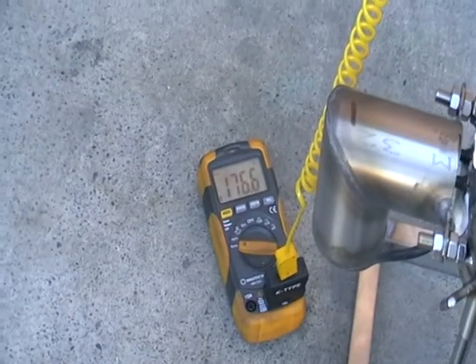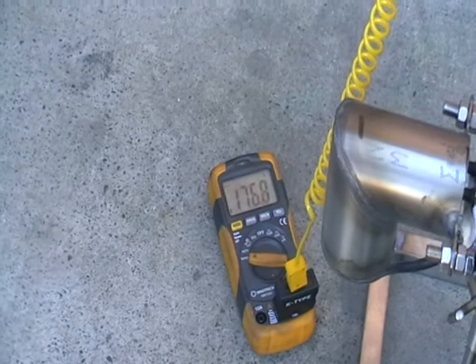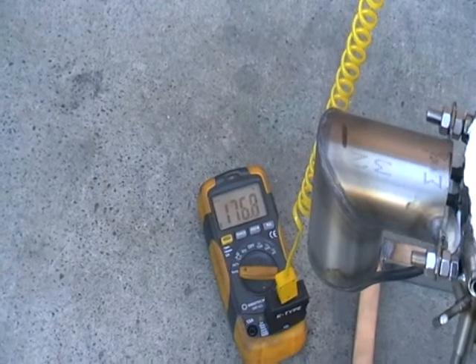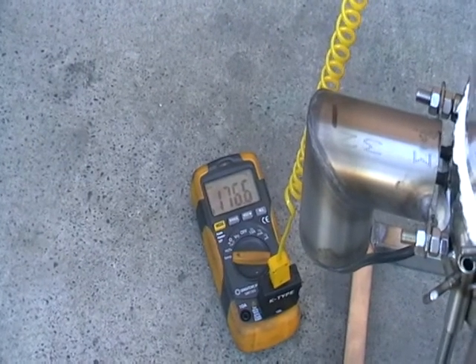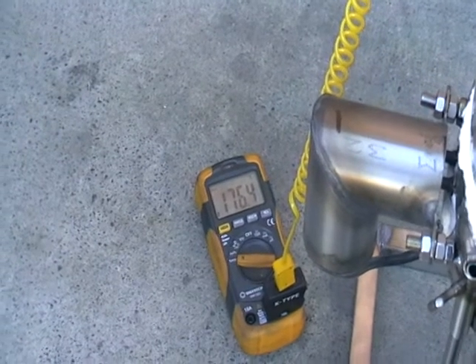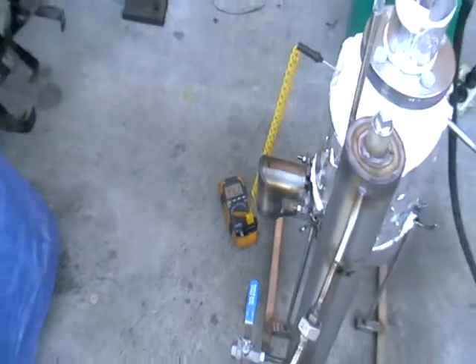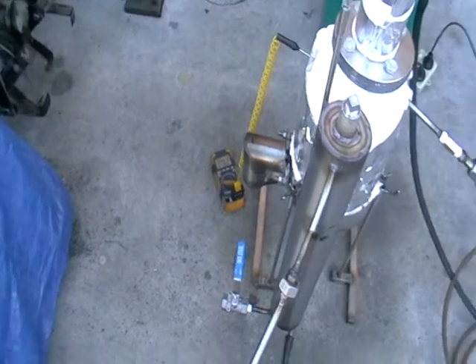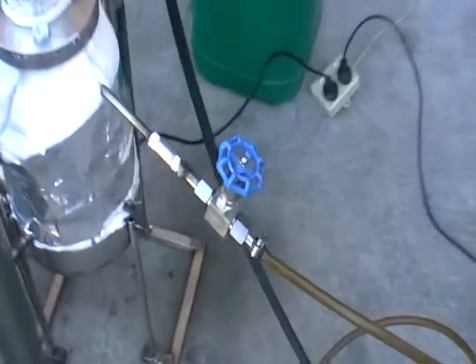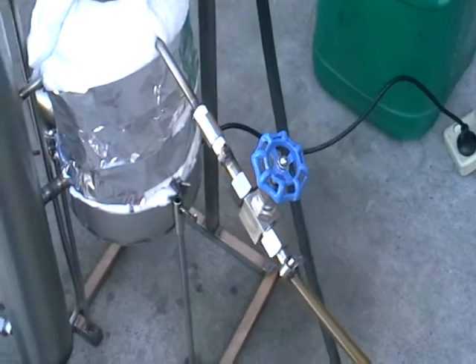Here's the temperature — it is relatively stable. It may fluctuate one degree up or one to two degrees down, but that's not a problem. So technically once you adjust it, it will keep the temperature for the whole period of production. This is a control valve — you control the flow, and the temperature is controlled by the flow.